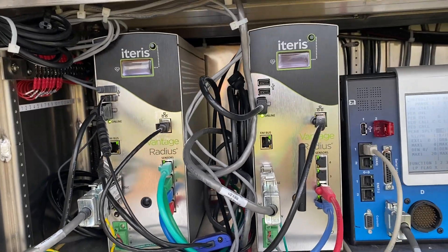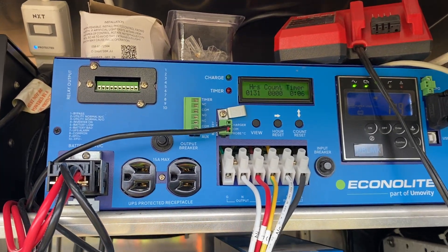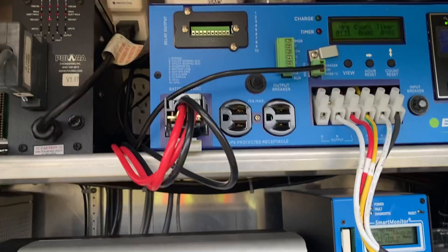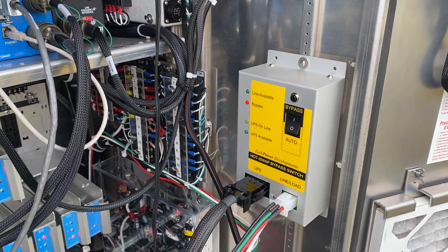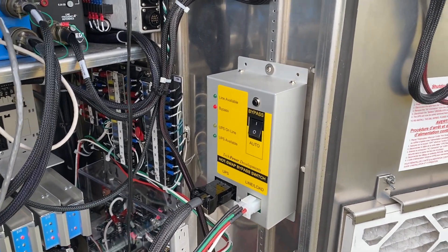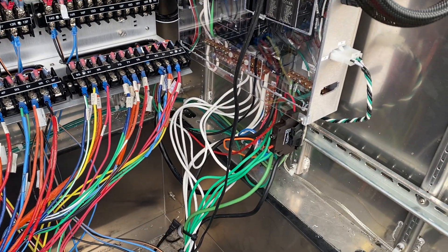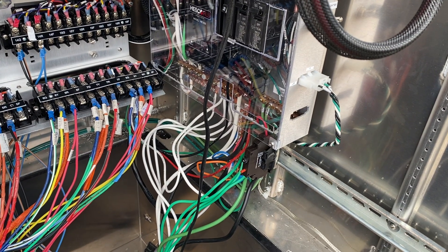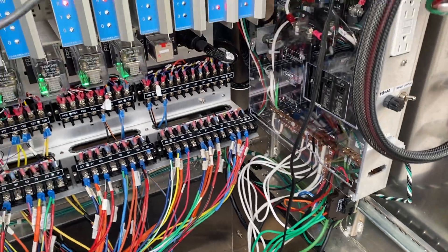We got the UPS unit here — power supply and load, all that stuff. Right now it's in bypass because I'm just allowing the batteries to charge. I just want to verify that that's working tonight. There's actually 240V at this panel, so I also have some heaters in the UPS cabinet, which runs on a separate leg since this cabinet draws a decent amount of power.